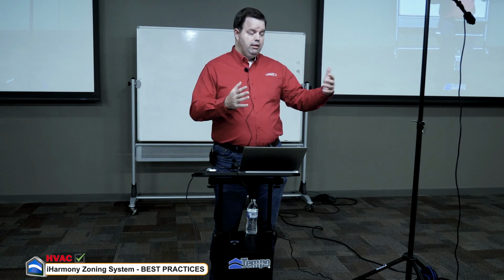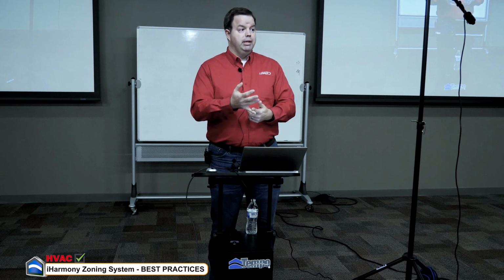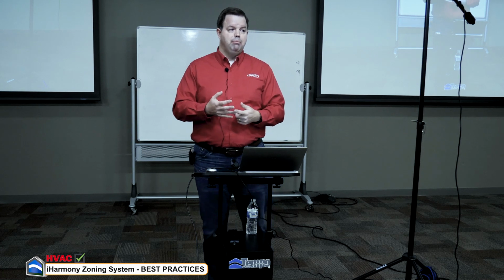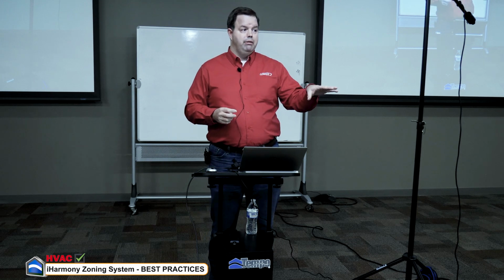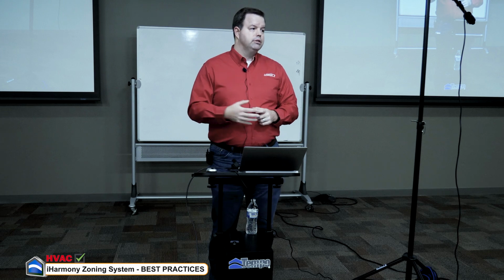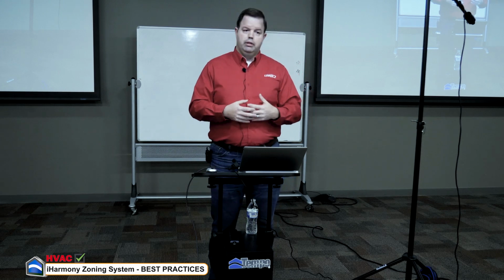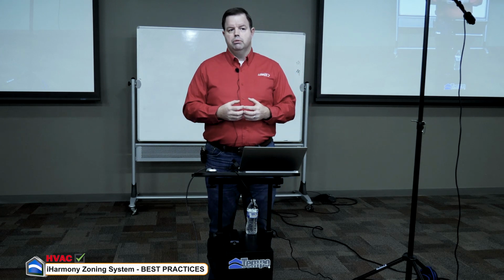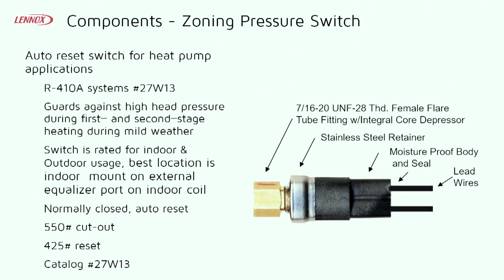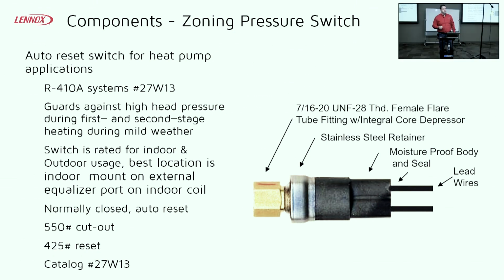You can look at the same thing for your outdoor unit. Like in the new SL28 outdoor unit or the SL25 heat pump, they have transducers in them now. So you can look at those pressures on the diagnostic screen for the AC unit or the heat pump and look at superheat and subcooling. That's a really great thing to have. But in the case of this switch, it's just there to say, hey, open or closed. It's not going to give you an actual pressure.